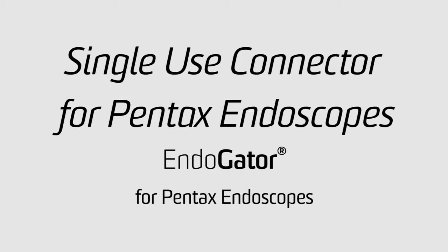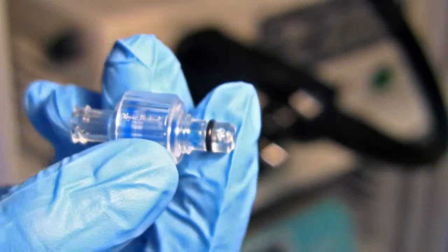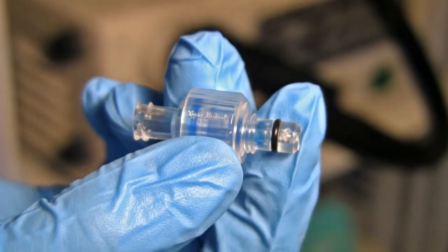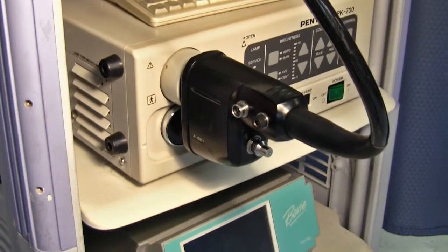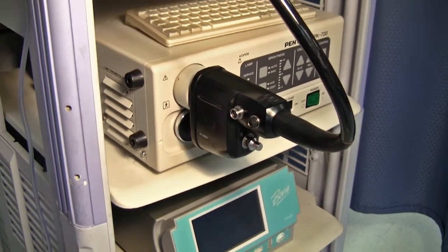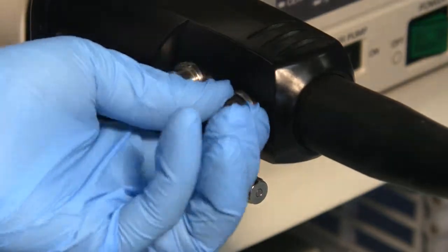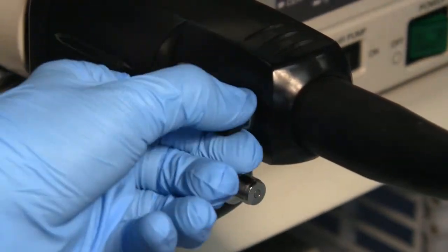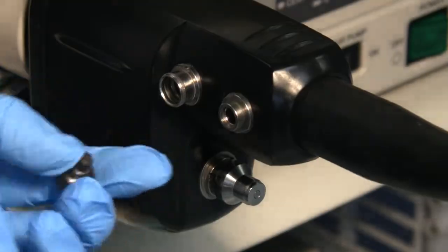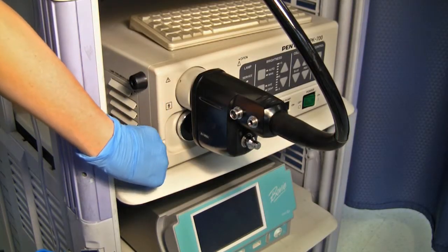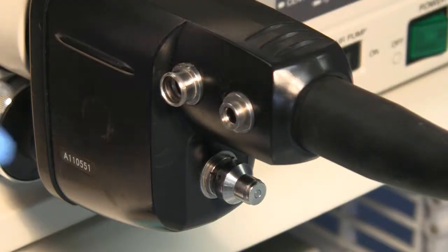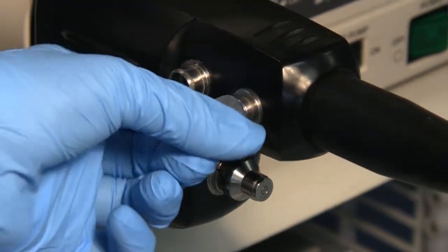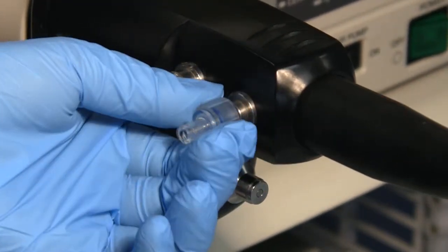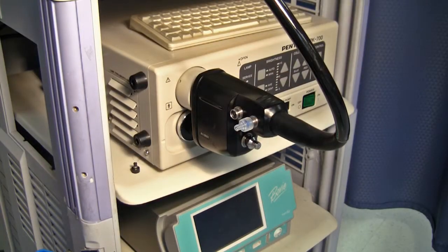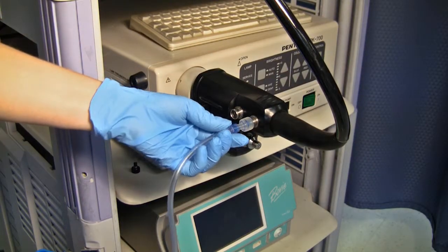Being a truly universal solution, all EndoGators can be used with any scope on the market today. In this section we have a Pentax scope and connector shown. With the Pentax scope, to use our single-use connector you must first remove the black water jet channel adapter. After you have done so, take the single-use connector and thread it onto the scope in a clockwise fashion. Then, luer lock the EndoGator tubing to the single-use Pentax connector.